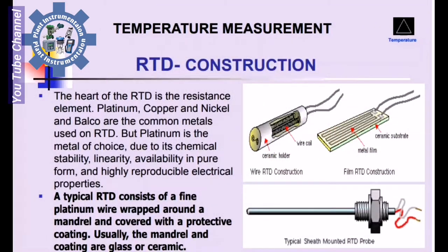RTD Construction: The heart of the RTD is the resistance element. Platinum, Copper, Nickel, and Balco are the common metals used in RTDs. But Platinum is the metal of choice due to its chemical stability, linearity, availability in pure form, and highly reproducible electrical properties.